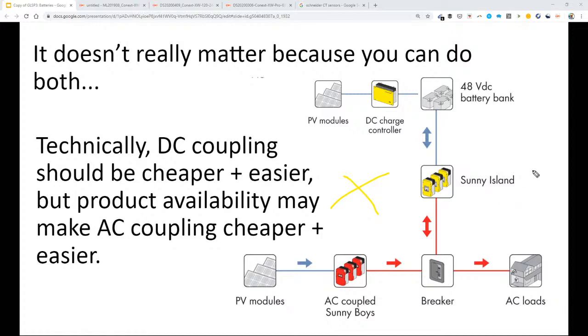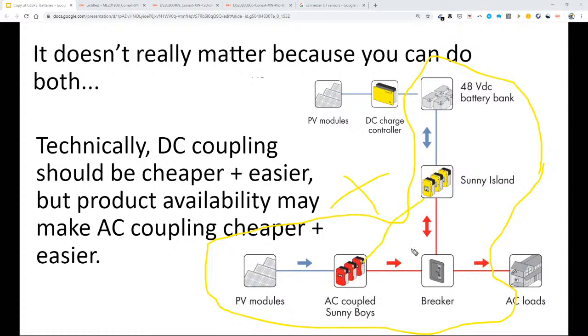The answer is, it doesn't matter—you can do both. In fact, I've found that AC coupling is a little more idiot-proof than DC coupling, if you're choosing just one. What's most important is sticking to one inverter manufacturer's product line throughout the system as much as you can. Not all inverter manufacturers make DC-coupled charge controller products.